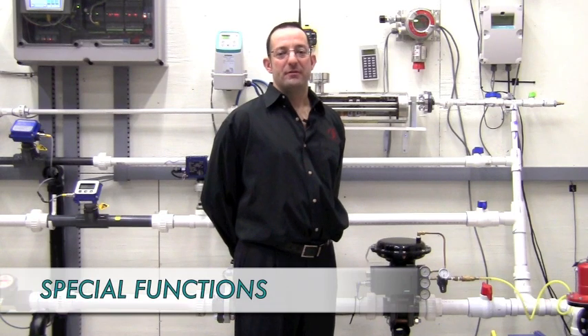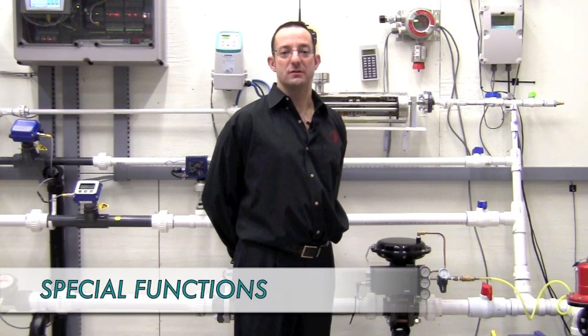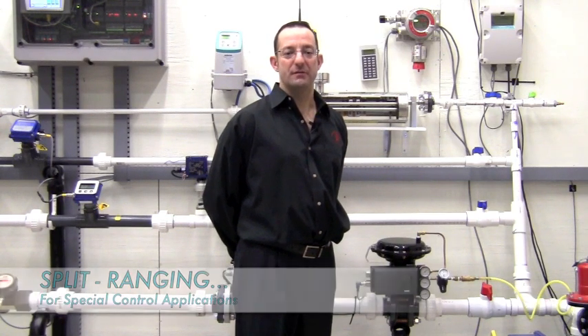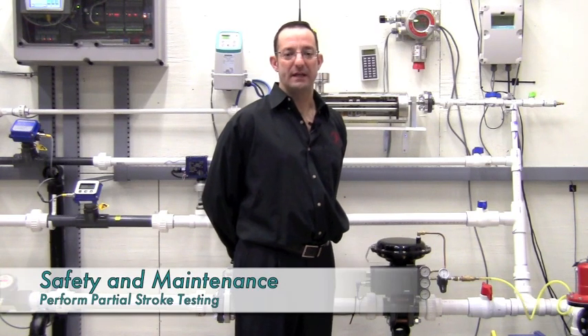Once calibrated for the valve, the PS2 can easily be set up to perform special functions. For control applications like split ranging, reversing the valve action, or limiting the stroke, you can configure settings for your particular needs once the initial setup is done.